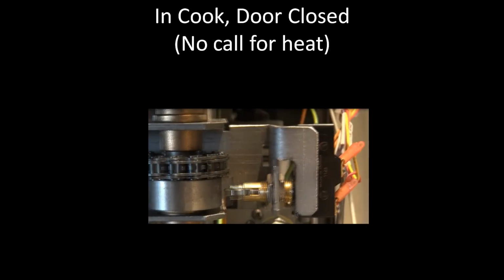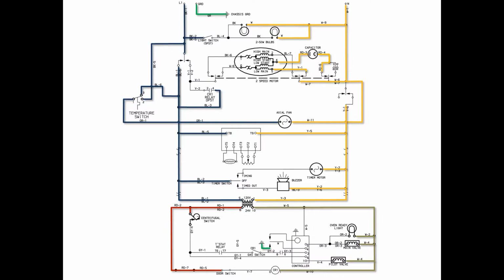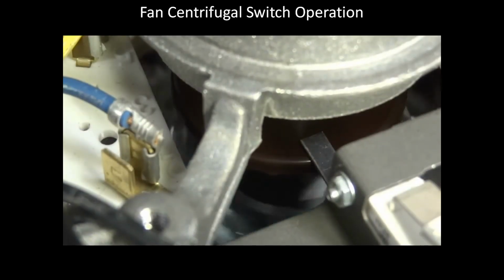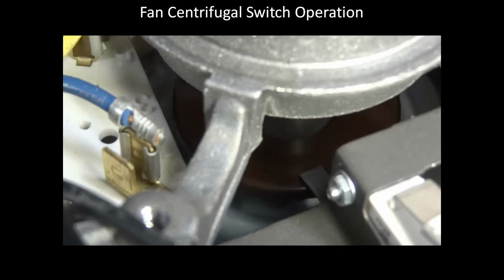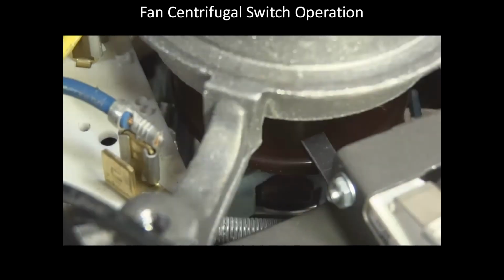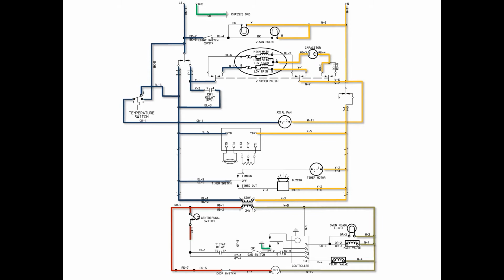Next, while still in cook mode, with no call for heat, we will close the door. The door switch sends voltage to CR1, and the relay then sends voltage to the motor through the high-low switch. When the motor rotates, the centrifugal switch closes. Here we see the switch close when the clutch in the motor drops. The centrifugal switch then feeds the thermostat relay and the blind terminal 6 of the ignition module. Note that the door switch also triggers CR1 to close these relay points, which are not yet used.